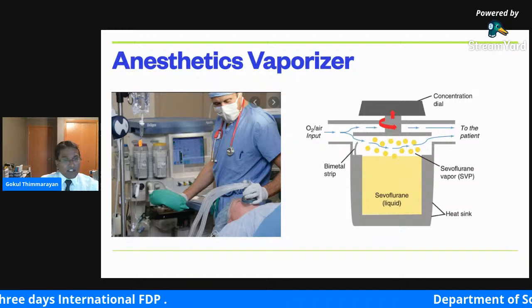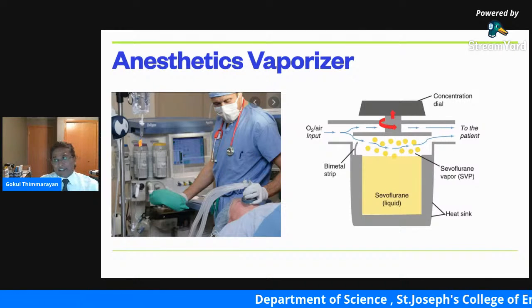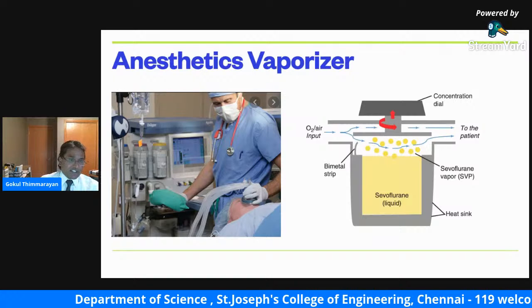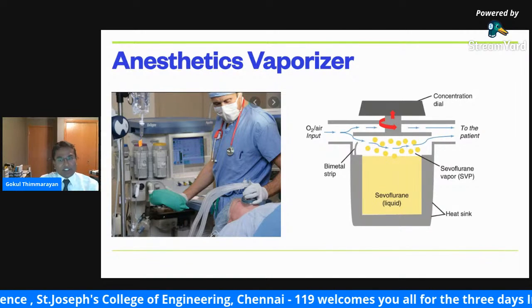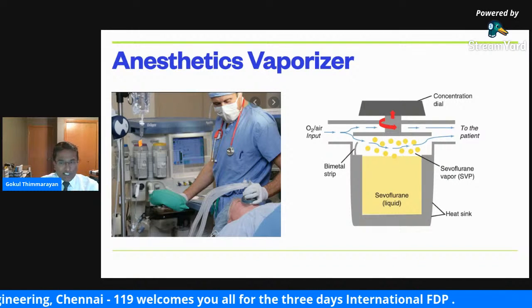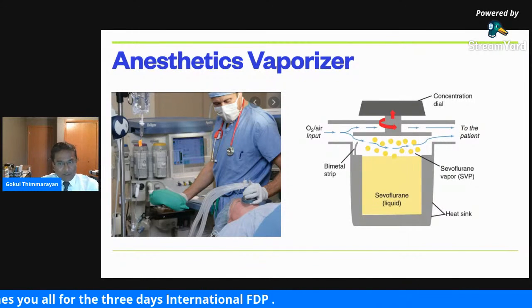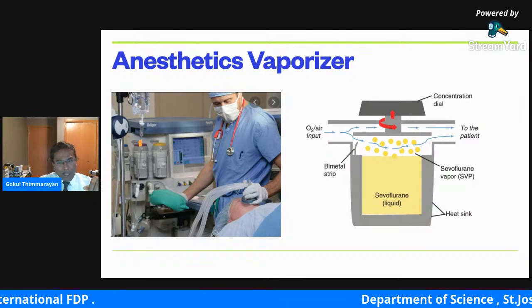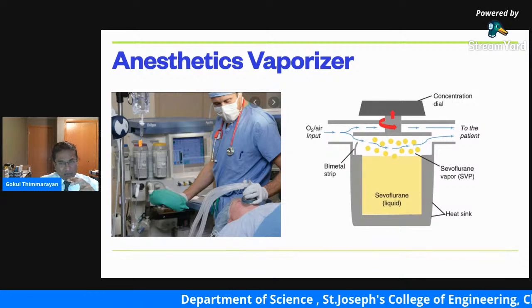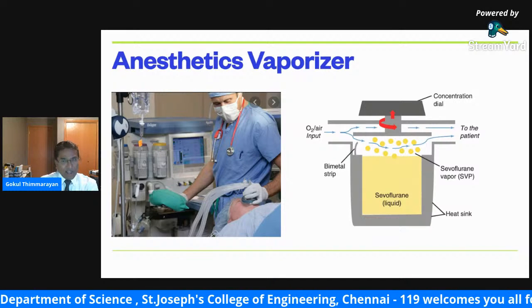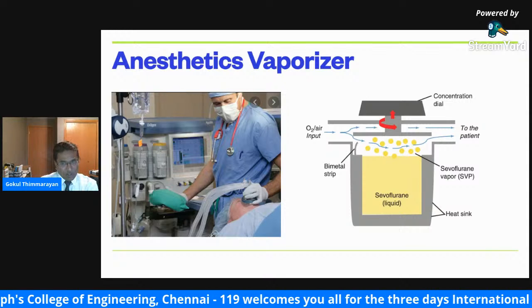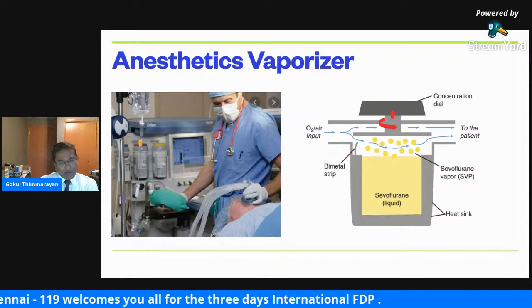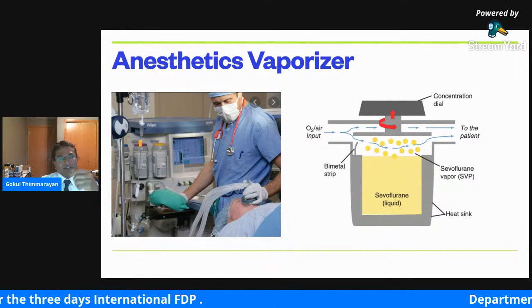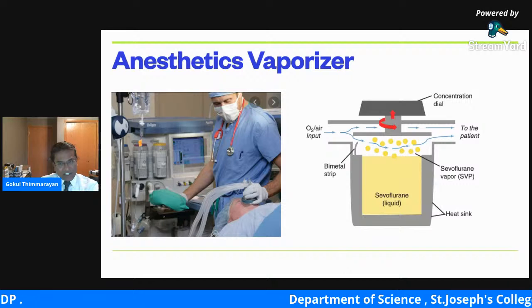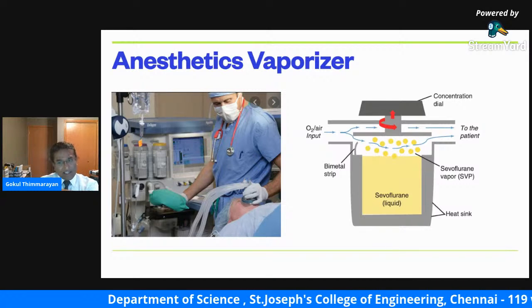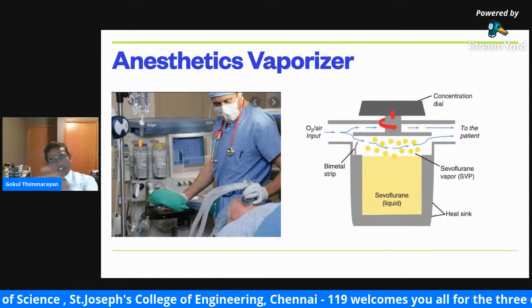So to deliver the desired, appropriate amount of anesthetic gas, the vaporizers, the canister-like device there, are utilized. It's called an anesthetic vaporizer. And to the right, on the picture, we see the longitudinal section of the vaporizer. So how the anesthetic gas is delivered to the patient is, oxygen is allowed to pass through the vaporizer, where there's a bypass chamber. In the vaporizer, below is the chamber where the anesthetic agent is stored. So when the oxygen passes through that, there are molecules of anesthetic agent vaporized, and they stay on the surface of the container. When the oxygen passes through it, it carries the anesthetic agent along with it, and it reaches the patient to anesthetize.